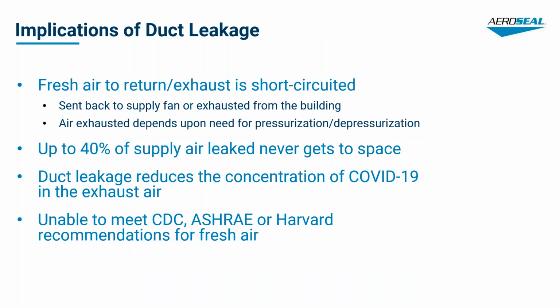So let's talk about those implications of duct leakage right now. Just like we talked about short circuiting when we were talking about energy savings, it's really the same thing that's causing the problems right now with the fresh air. So the fresh air to the return or the exhaust is being short circuited. So it's sent back to the supply fan or being exhausted from the building, and the exhausted air depends on the need for pressurization or depressurization. Up to 40% of the supply air that's being leaked never gets to the space. And the duct leakage reduces the concentration of the COVID in the exhaust air. All of this means that you're unable to meet CDC, ASHRAE, or Harvard recommendations for healthy buildings; you're never going to be able to meet that for fresh air in buildings.